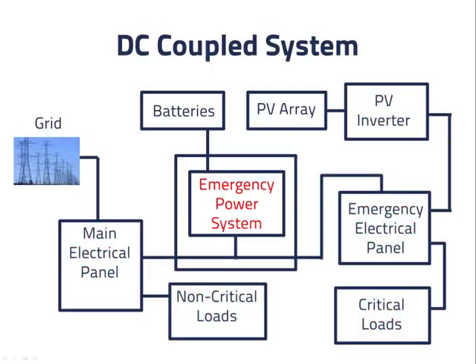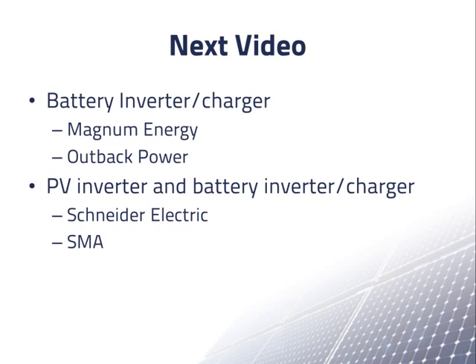The block labeled emergency power system contains the battery inverter charger. This could be a grid interactive inverter charger so it could put out power from the battery in parallel with the grid — one might do this if there is a power shortage or if the grid operators are paying a high price. However, in practice, all battery inverter chargers sold for AC coupled PV systems are not grid interactive: when connected to the grid, they work only as chargers, and only work as inverters when disconnected from the grid. In the next video, we will discuss equipment developed or modified for AC coupled grid connected PV systems with batteries, including companies that make battery inverter chargers compatible with other companies' grid connected inverters, and companies that make both PV inverters and battery inverter chargers that can be integrated.